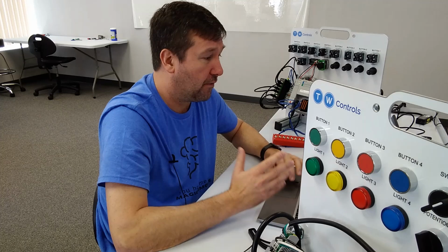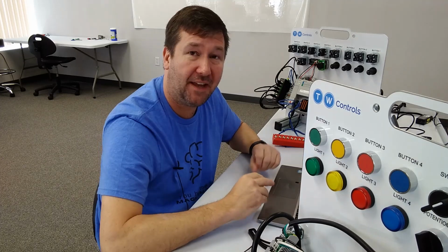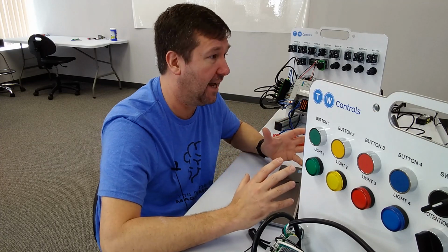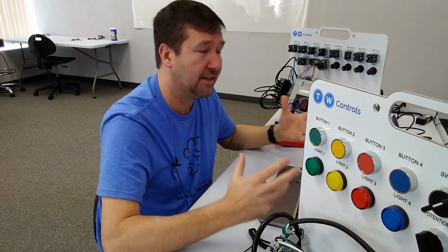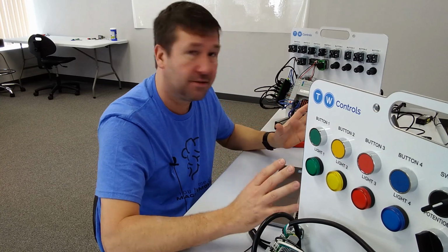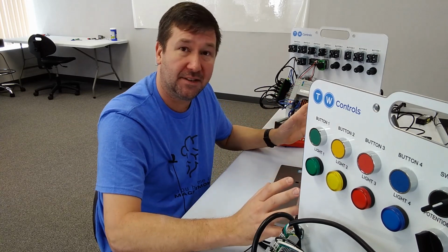And finally, if you do have a program that uses an intense amount of produce and consume tags, you can right-click up here on the column headings, and you can add base tag to the monitor tags part. So now we have it there. Maybe we decide we want it right over here. We can just drag it over. And now we can clearly see here that this is the base tag. So that covers how to use produce and consume tags. And really, this does replace messaging on Studio 5000 style PLCs.